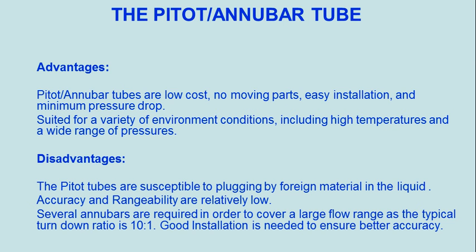Pitot and annubar tubes offer advantages of low cost, no moving parts, easy installation, and minimum pressure drop, suited for a variety of environmental conditions including high temperatures and a wide range of pressures. Disadvantages include susceptibility to plugging by foreign material in the liquid, and relatively low accuracy and rangeability. Several annubars are required to cover large flow ranges. The turn-down ratio is 10:1, and good installation is needed to ensure better accuracy.